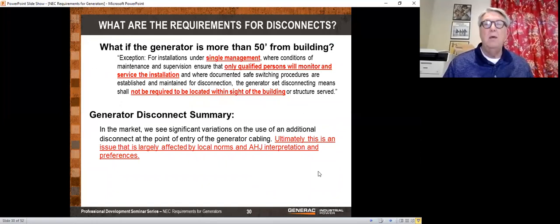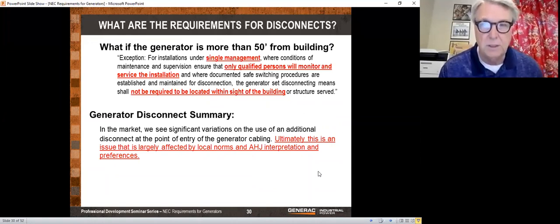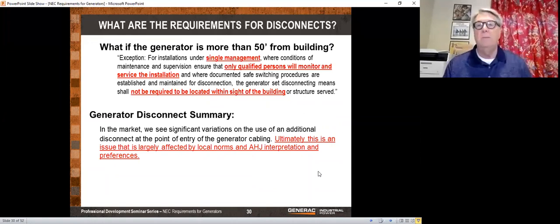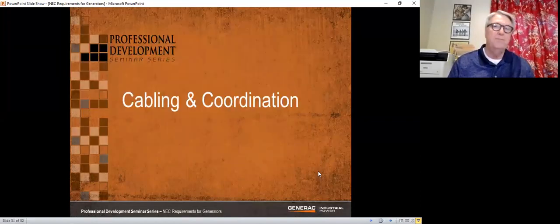accessible. Now, what if the generator is more than 50 feet from the building? Well, it says for installations under single management where conditions of maintenance and supervision ensure that only qualified persons will monitor and service the installation, and where documented safe switching procedures are established and maintained for disconnection, the generator set disconnecting means shall not be required to be located within sight of the building. So there is an exception for that.